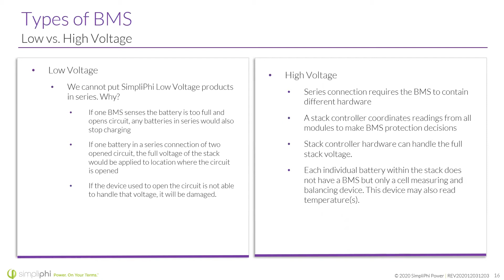High voltage systems are obviously a bit different. They're designed for a series connection, and whatever's opening that circuit, the hardware is designed to handle the full stack voltage. Additionally, within a high voltage stack, each individual battery does not have a single BMS per battery, but each battery is going to have basically a cell measuring and balancing device. This device might also read temperatures, it may or may not.